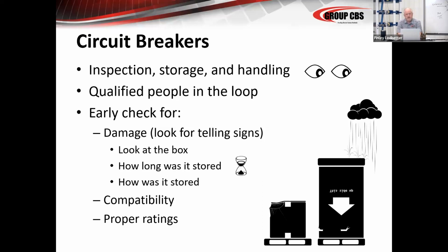The next thing is compatibility. Quite often we see breakers that come to switchgear to be inserted in switchgear, and they're either the wrong breaker. Breaker A was supposed to go with substation B. Breaker B was supposed to go with substation A, that sort of thing. So check the compatibility and check for the proper ratings. You should have a schedule of what those ratings should be, and make sure someone with enough experience looks at the breakers to make sure you're getting the proper ratings and the proper cells.